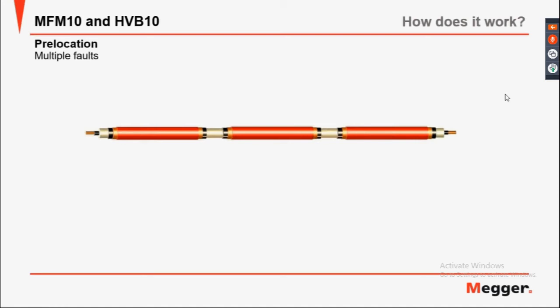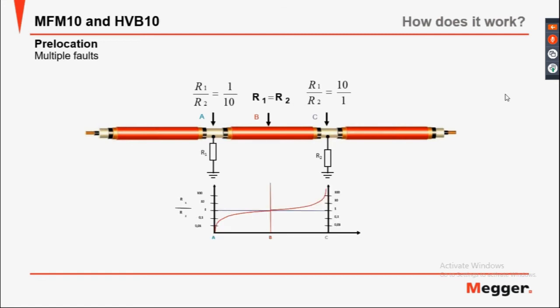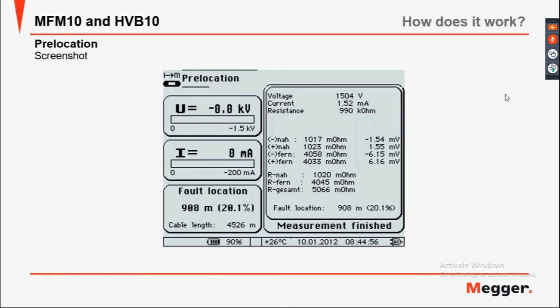Prelocation of multiple faults: when there are two faults with very similar resistances, the pre-location will give a result midway between the two faults, as a virtual point is indicated depending on the resistances. The closer the resistances are together, the more equal the result will be between them. If one fault has a higher resistance, the lower resistance fault will appear closer to it. The pre-location screen shows near-end and far-end resistances and voltages.